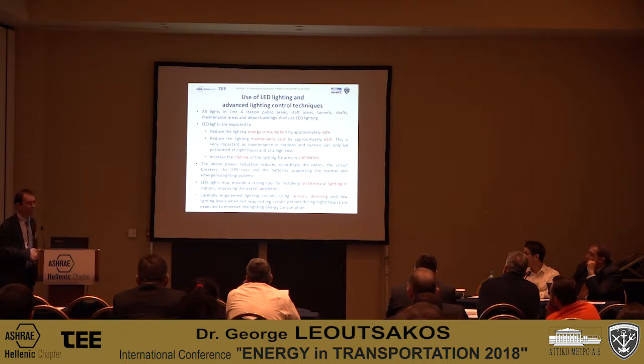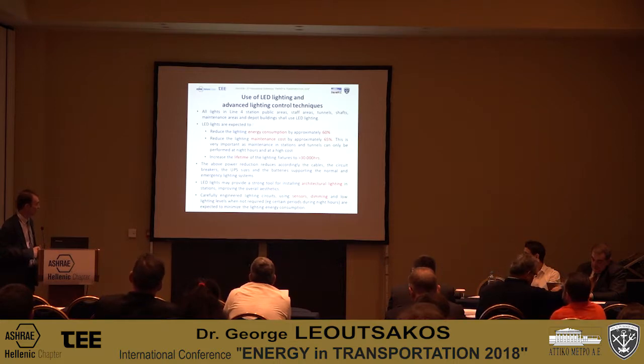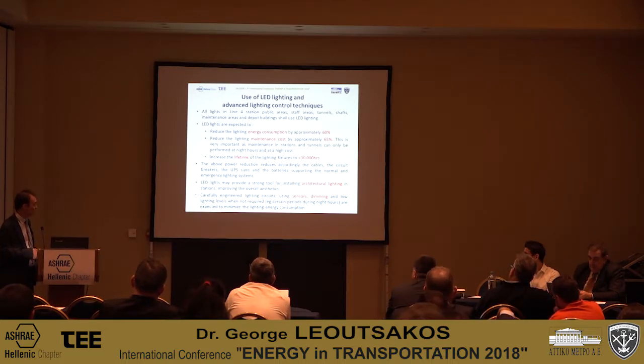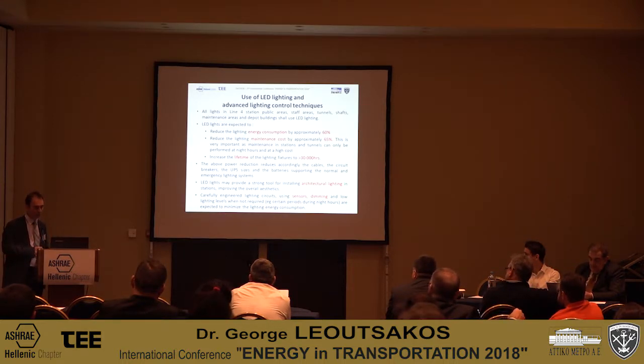This is mainly because maintenance in a metro system is done during night hours, which costs even more. LED will increase the lifetime of the lighting fixtures. It also has other advantages: it will reduce the cabling for lighting, the circuit breakers, the switchboards - everything will become smaller - the UPS sizes, and the batteries supporting these lighting systems. Also, since we have to work together with the architectural side of designing metro stations, LED lighting can greatly improve architectural lighting as well.